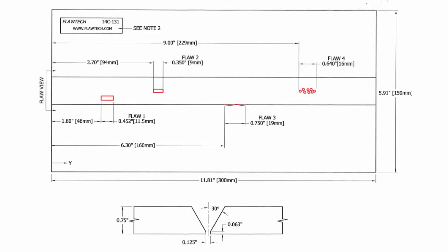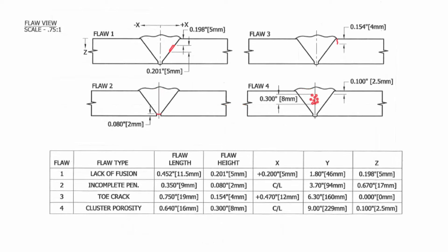The weld considered in this demo is a carbon steel weld plate with a nominal wall thickness of 19mm or three-quarters of an inch. It has a commonly used V-type bevel and contains typical welding defects: lack of fusion, incomplete penetration, a toe crack, and a cluster of porosity.